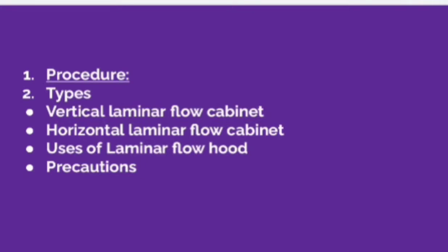And in last, precautions. While operating the laminar airflow cabinet, the following things should be considered. The laminar flow cabinet should be sterilized with the UV light before and after the operation. The UV light and airflow should not be used at the same time. No operations should be carried out when the UV light is switched on. The operator should be dressed in lab coats and long gloves.